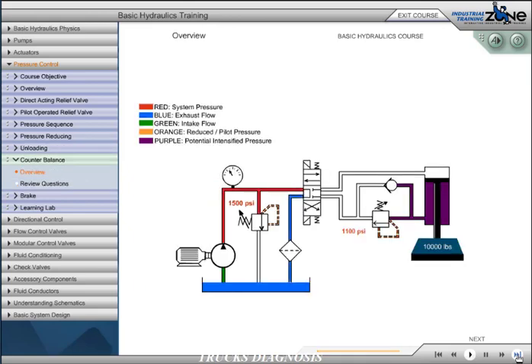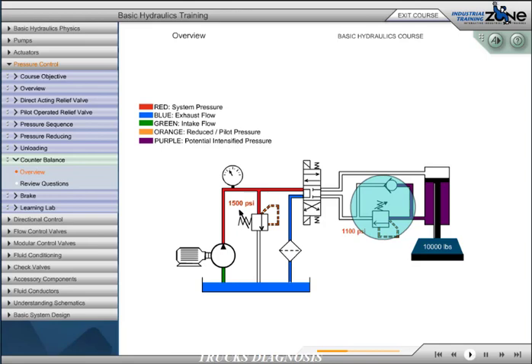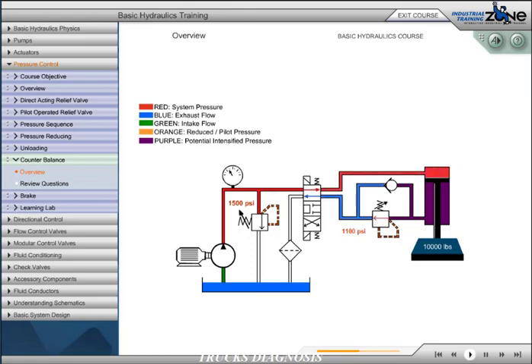A counterbalance valve is a normally closed pressure valve used with cylinders to counter a weight or potentially overrunning load. In this circuit, without a counterbalance valve, the load would fall uncontrolled or overrun, and pump flow would not be able to keep up. To avoid the uncontrolled operation, we place a counterbalance valve just after the cylinder. The pressure setting of the counterbalance valve is set slightly above the load-induced pressure of 1,000 PSI. This counters the load.